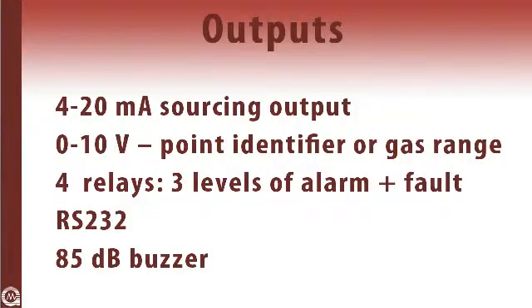The PA4000 has a 4 to 20 milliamp sourcing output as well as a 0 to 10 volt output that can be used to identify the sample point to a PLC or DCS. It has three relays for the concentration of the target gas and one fault relay. An RS232 output is standard along with an 85 dB buzzer.